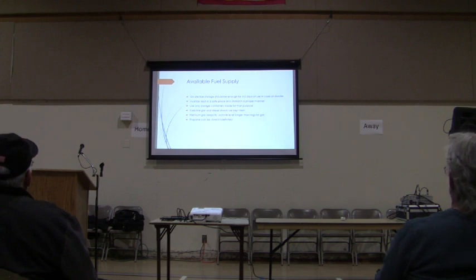So how much fuel do I need? Once you pick your generator, you're looking for on-site fuel storage to be enough for 3 to 5 days. It needs to be kept in a safe place and stored in a proper manner away from a running generator. Use only storage containers made for that purpose. Fuels like gas and diesel should be kept as fresh as possible, if not stabilized.